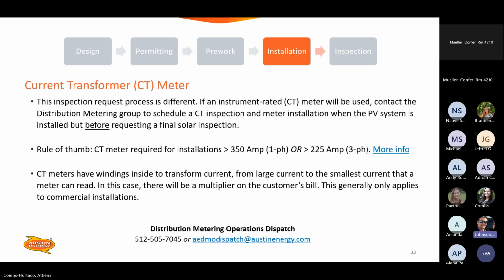So a current transformer, a CT type meter, these are usually for single phase 350 amps or larger, or 3-phase 225 amps or larger. These are different from a general regular bypass handled meter. This inspection request process is different. If an instrument rated CT meter will be used, contact DMO, Distribution Metering Group, to schedule a CT inspection and meter installation, but you must do this before requesting the final solar inspection.